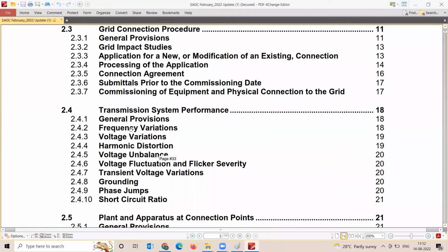One of the recent harmonic measurements we had was in one of the plants, a 250 megawatt solar plant, and 3 such solar parks are connecting to a common 220 kV substation, which means about 750 megawatts. Though this plant does not inject heavy harmonics, thanks to the other 250 megawatt plants, it is facing a problem, right?